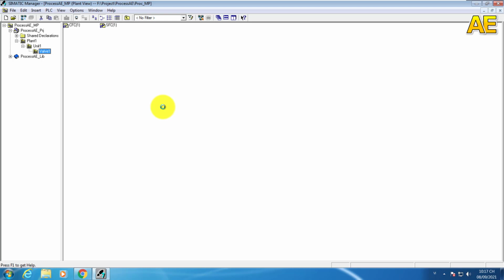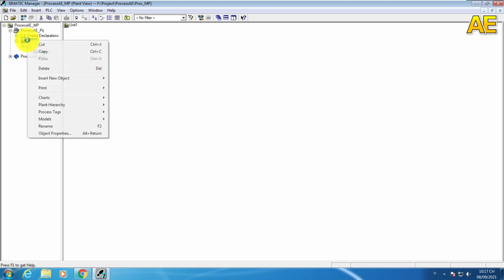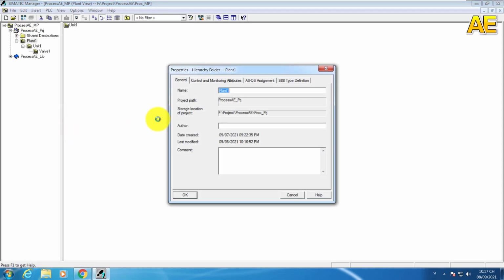The plant view is a logical representation of the project, so the objects of the plant have to be assigned to the AS and OS in order to be executed. So one plant folder here will be assigned to one AS and one OS. To do that, right click on the plant folder here, select the object properties. You come to the AS/OS assignment tab.